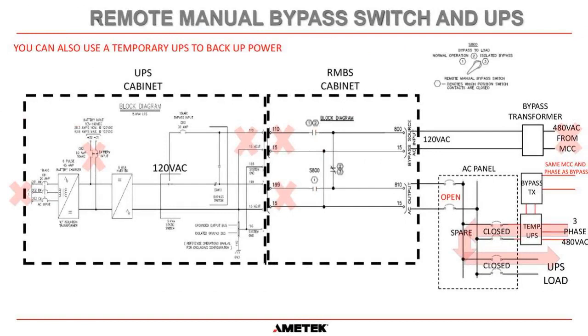It's a little bit more expensive way to get around it, because what you need to do is, instead of just installing a temporary transformer, what you can do is actually install a temporary UPS to backfeed the system. And if you do that, this temporary UPS is going to have its own battery. So you are going to feed power to your UPS loads this way. And if you do have a power outage while you are installing this RMBS cabinet, then this temporary UPS will sustain power during the outage to allow you to do whatever you need to do.